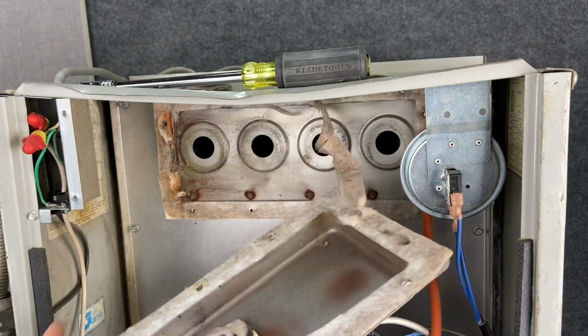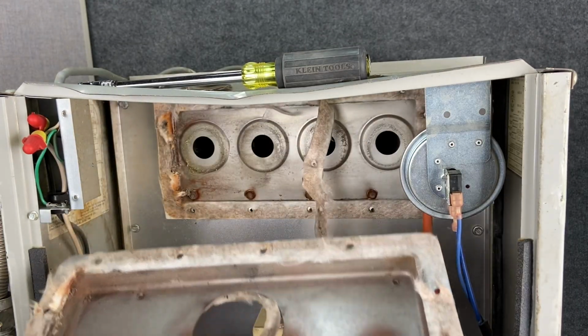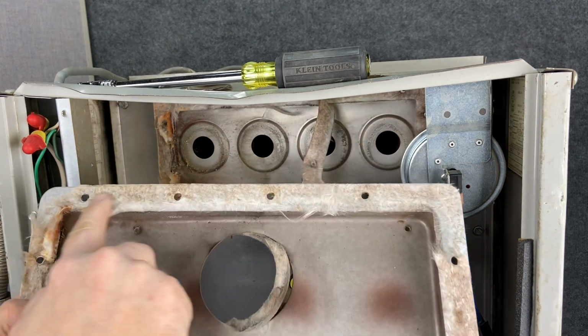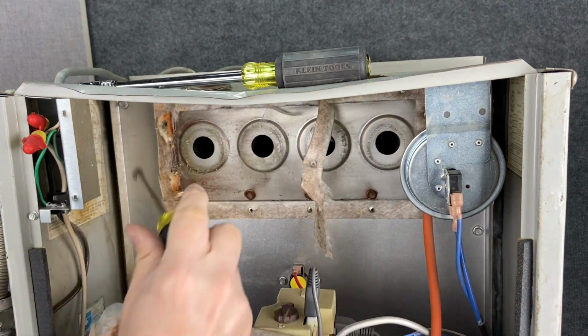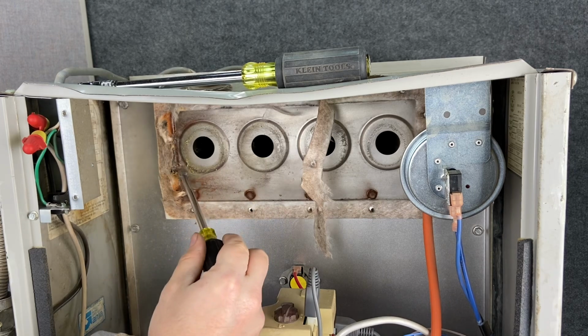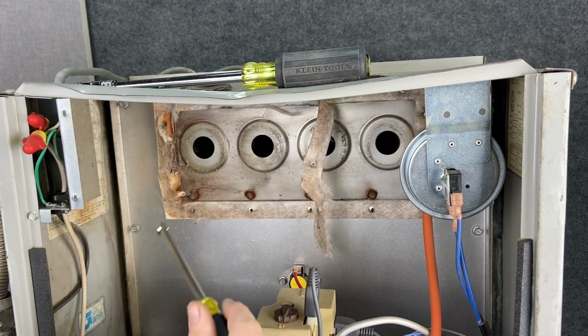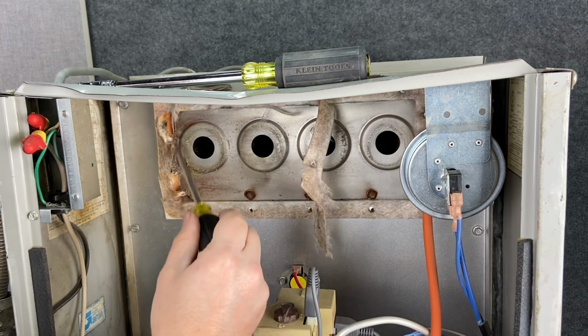Now as we take this collector box off, you notice it also has its gasket material on it that seals it up. You can see there's a significant amount of rust built up on this side, and there's a lot of corrosion in here. This was a horizontal furnace, so this was the bottom side.